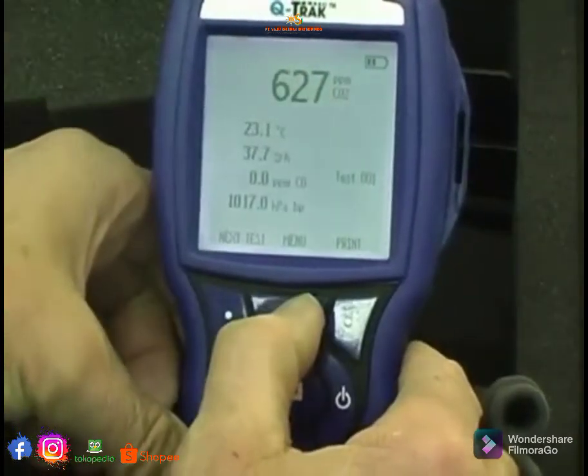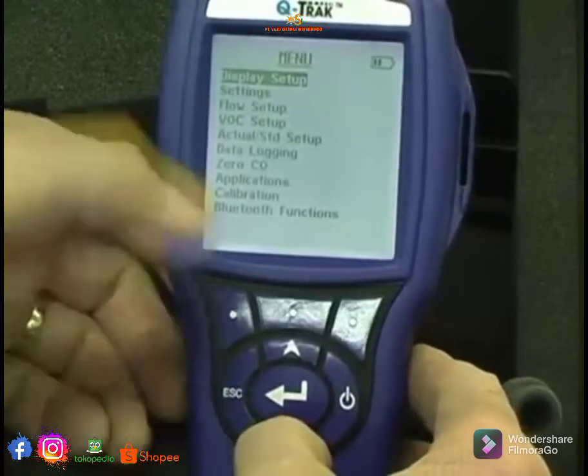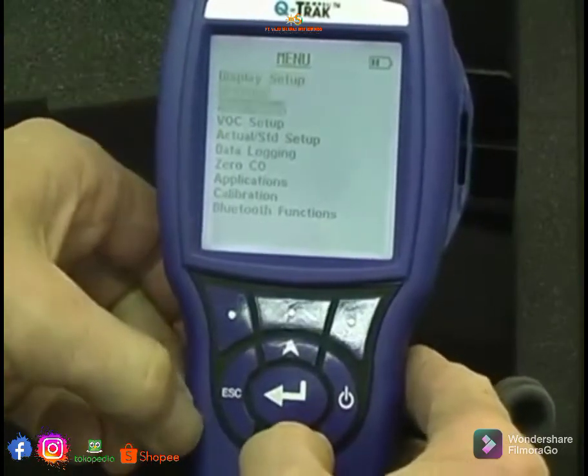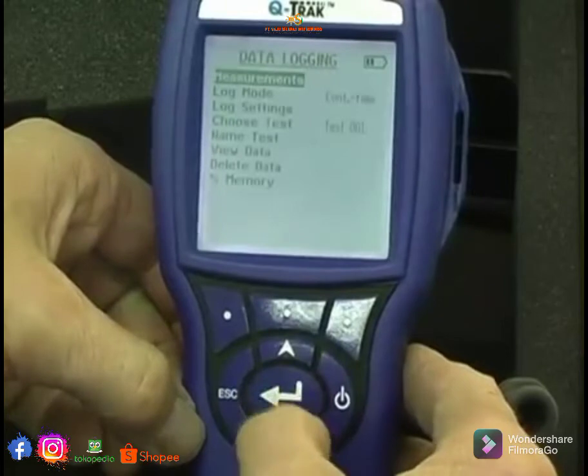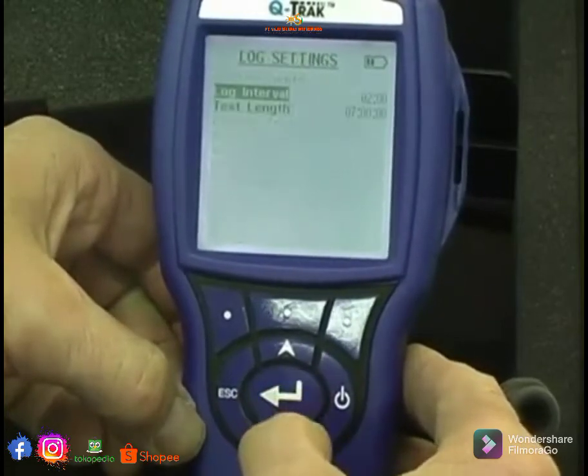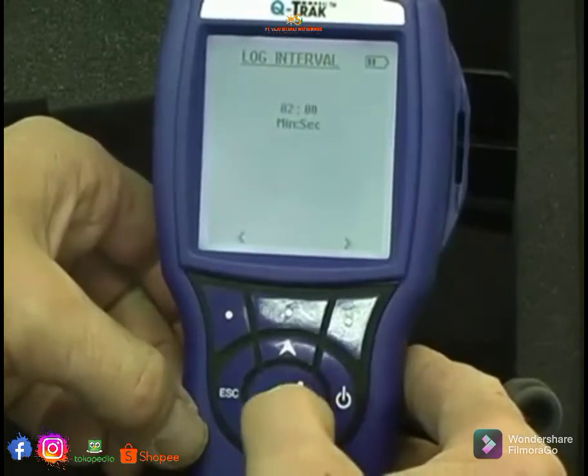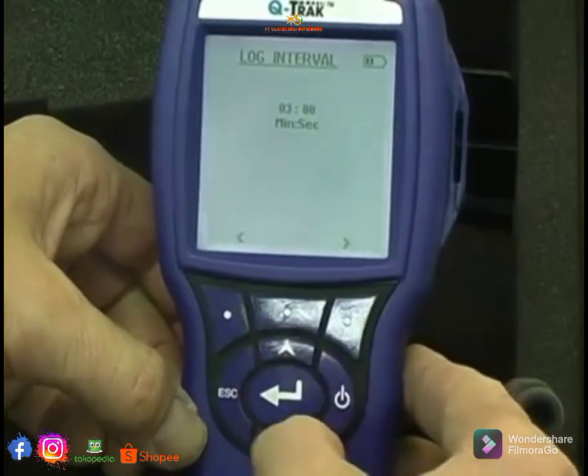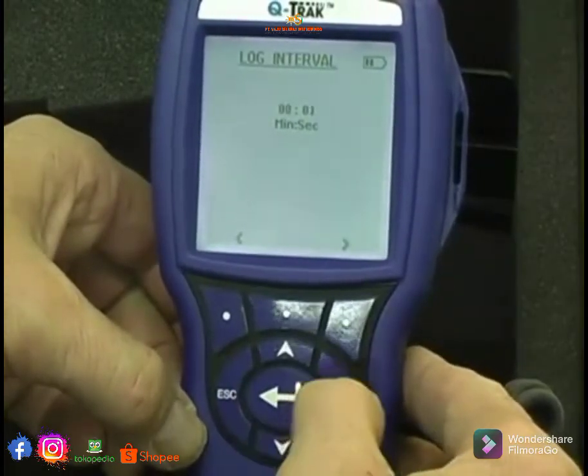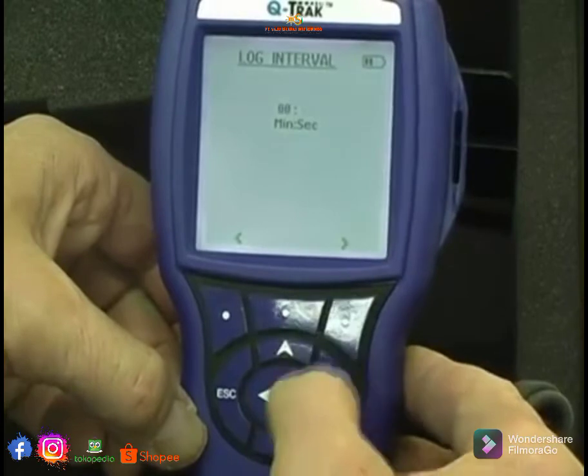I've hit escape, that's turned the data logging off. One of the other things you can do is disable the keyboard if necessary, but I'm going to turn the data logging on, continuous time, logger settings. In this case, interval again, I'm going to set it to 30 seconds. So here we go.